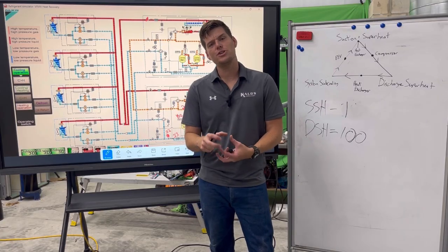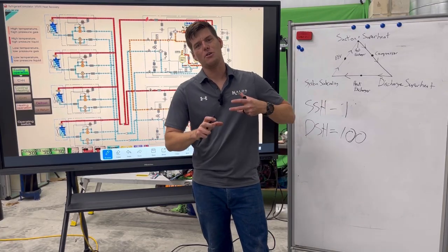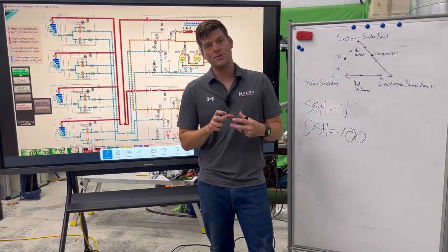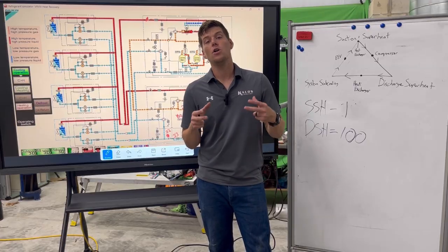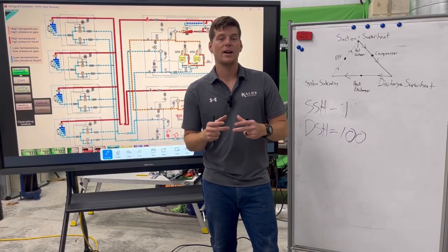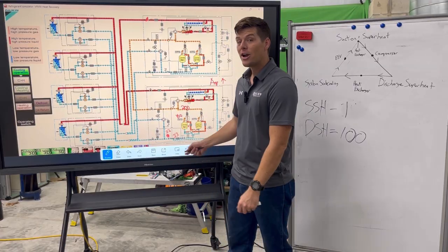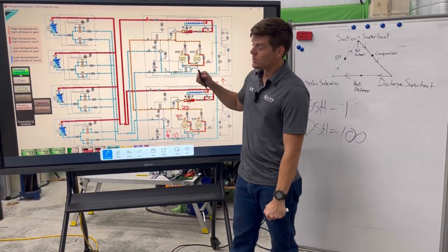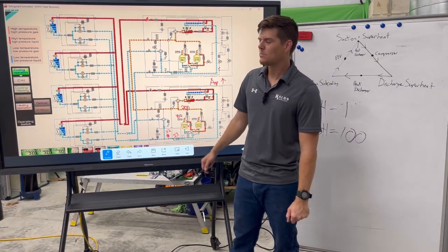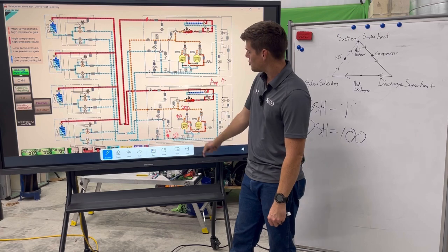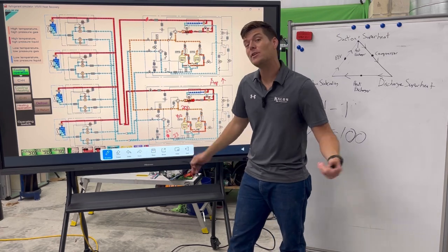When there's excessive friction and actual plates rubbing against each other, metal on metal, and that friction that's being created, there's also going to be a higher load on that rotor, on that stator within that compressor, and it's going to result in higher elevated amp draws. This compressor is close to pulling nameplate amps. This compressor is close to pulling amps to shut the system down. It's probably an overcurrent shutdown right now.